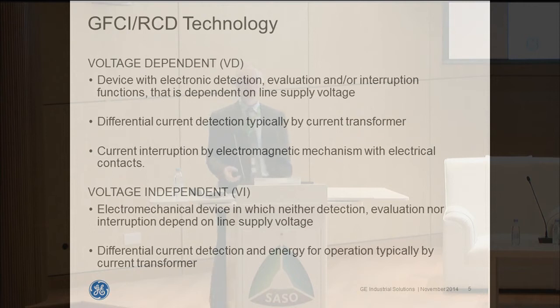When you look at the types of devices that are on the market today and globally, there's voltage-dependent devices, and these really are devices that tend to be electronic in nature, basically the NEMA style devices used typically in North America. They'll use current transformers to identify faults, and they will have the use of some kind of an electromagnetic trip function in order to interrupt the current. There's also voltage independent devices, typically called residual current devices, and these are electromechanical devices, and they do not necessarily require the use of a separate trip circuit to trip them.